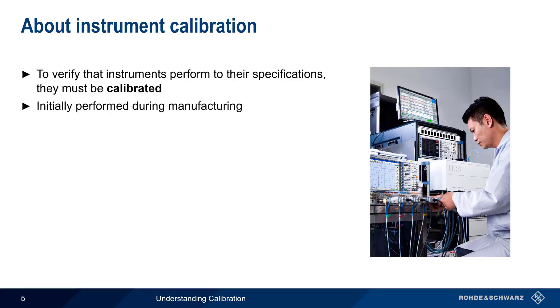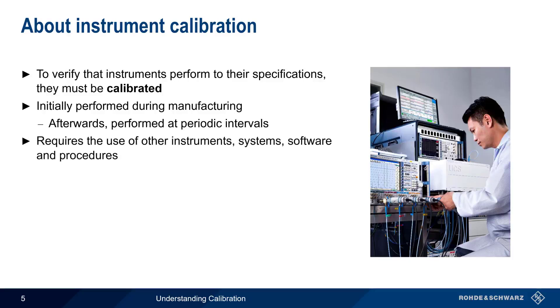An initial calibration of an instrument is performed during the manufacturing process, and for most types of instruments, calibration should then be performed at periodic intervals. In most cases, these time intervals are on the order of a year or more. The calibration process requires the use of other instruments, often integrated into special systems, as well as carefully designed software and procedures. In order to ensure the validity of the results, calibration should always be performed by trained calibration specialists.